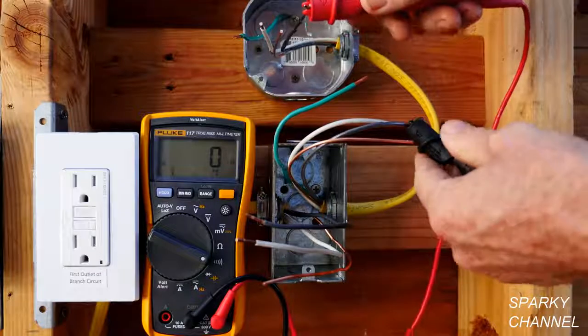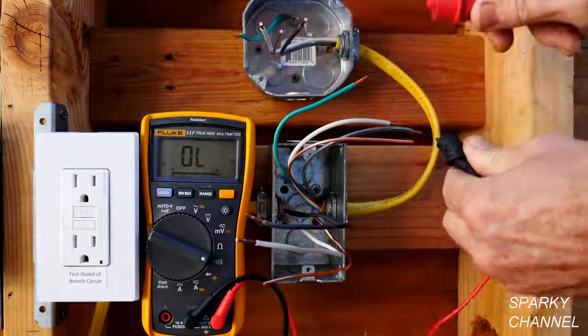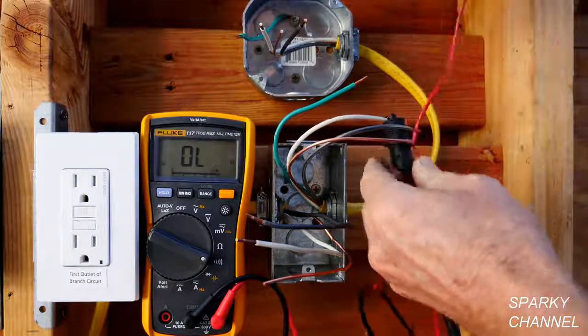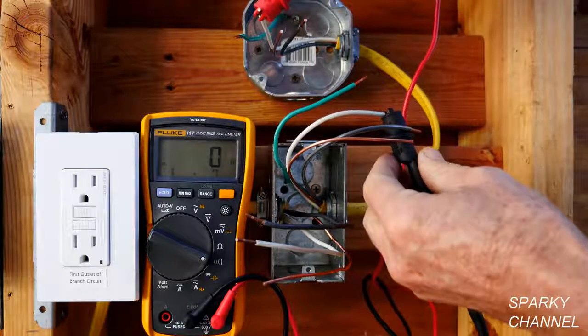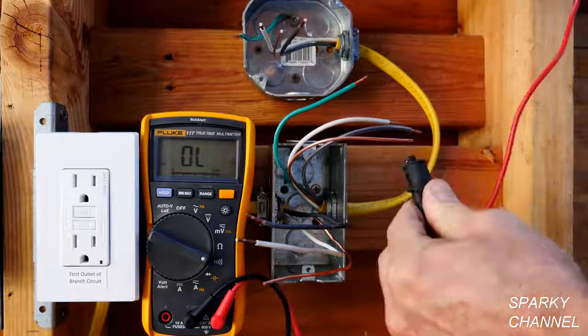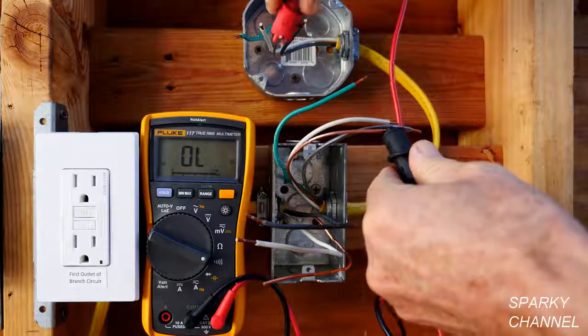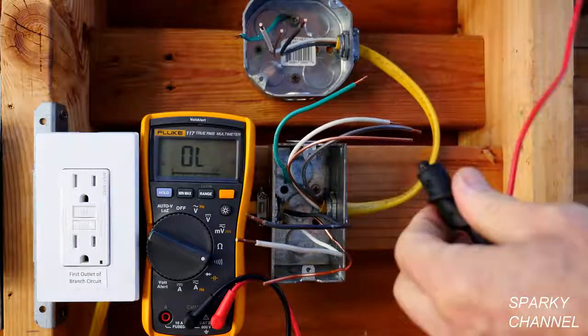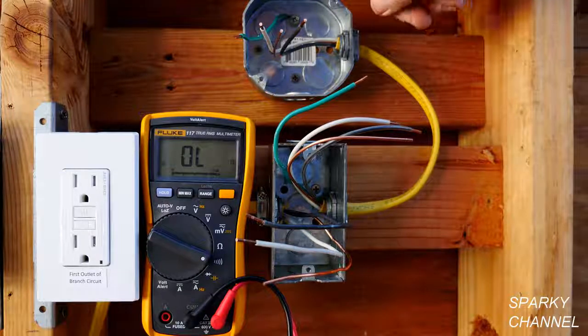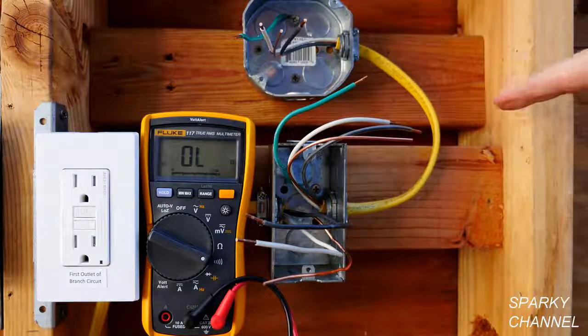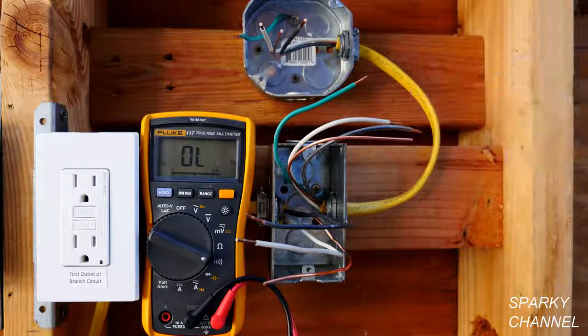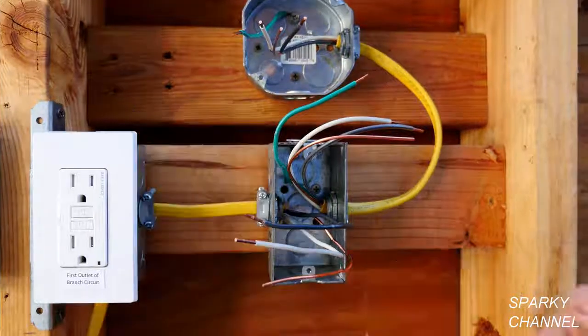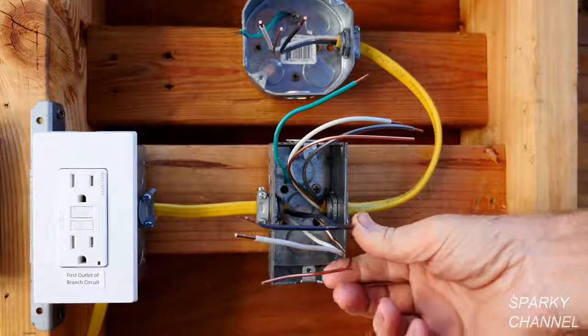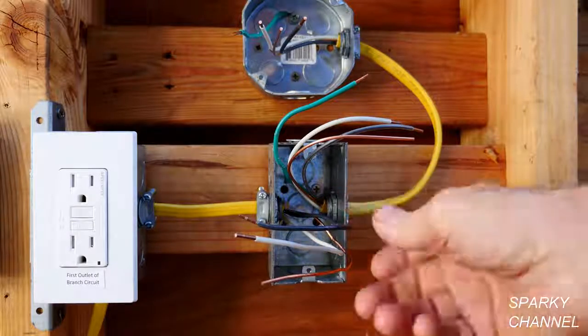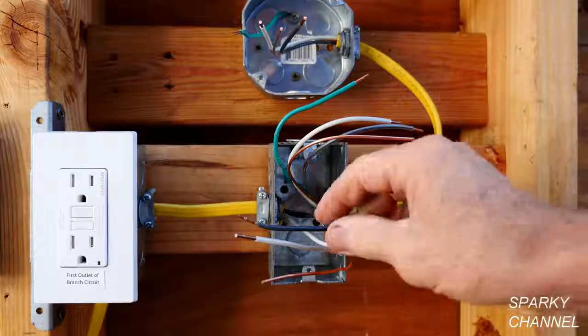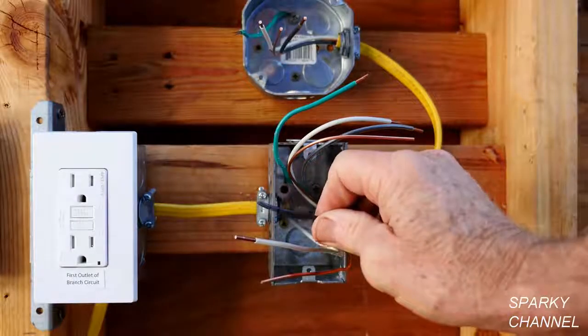So this is continuous, and I can test it with the neutral wire, neutral and neutral. Okay, that's continuous, and ground and ground, that's continuous. So this is indeed the light box that is going to be served by this switch, and the electricity is once again off. Since this is the cable that brings the electrical energy into this box, it is called the line cable, and this specifically would be called a line wire.